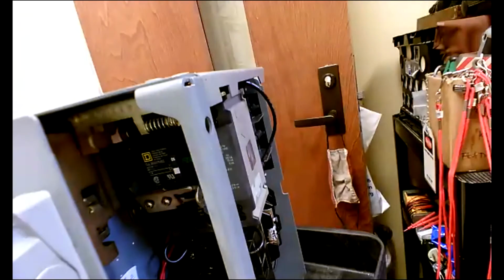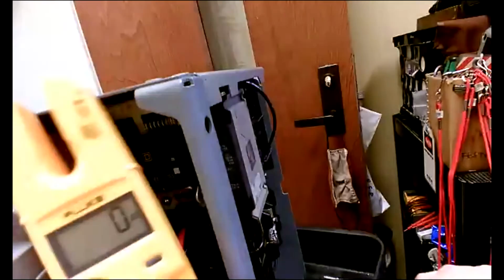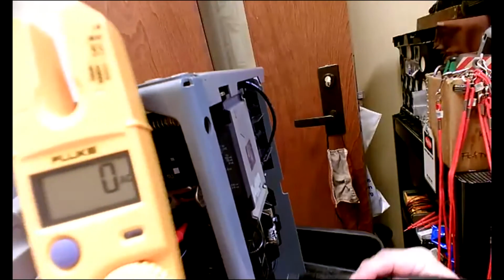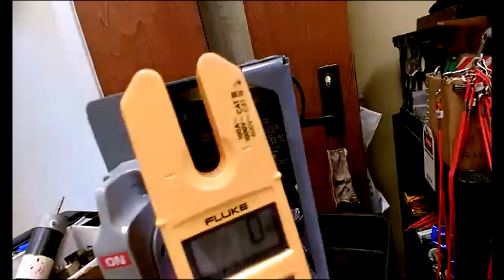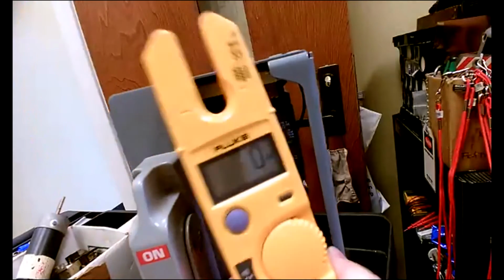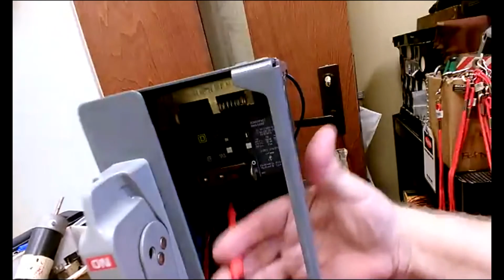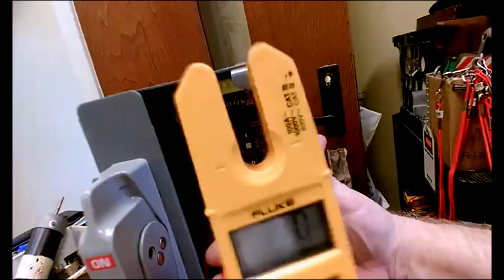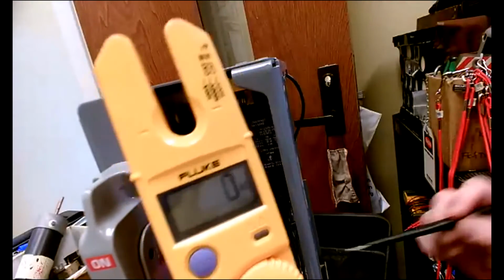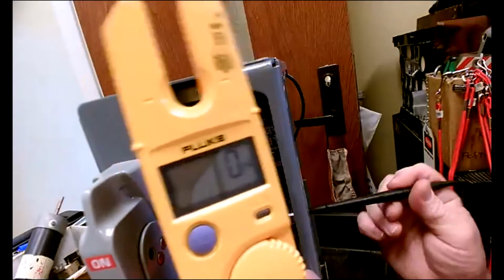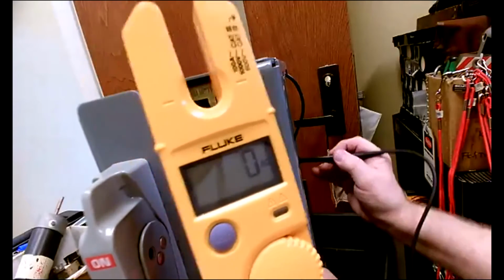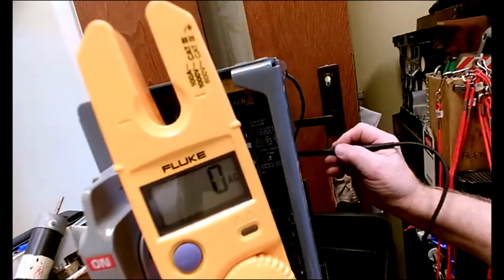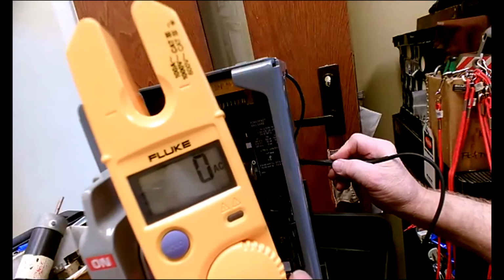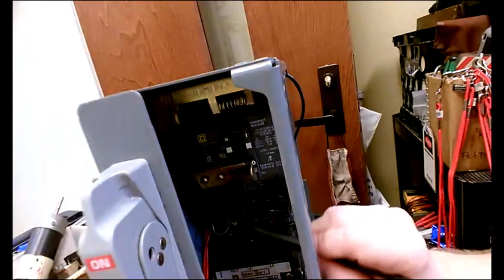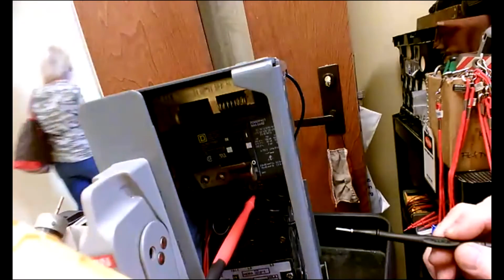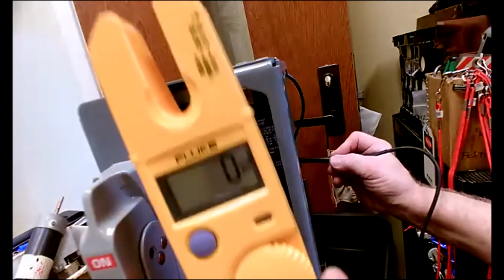So if I go, I've got to get the meter position right. If I go and check one of the hot wires in there, I go inside where the breaker is, and I'm checking one of the hot wires leaving the breaker. There's actually three of them in there. And I find me a ground point in this panel, a place I can get in contact with ground. I'm finding me a ground screw right in here. So the meter says 0, right? So that first leg on the breaker is dead. Then I go to the next leg on the breaker, and I go to ground, and it says 0.